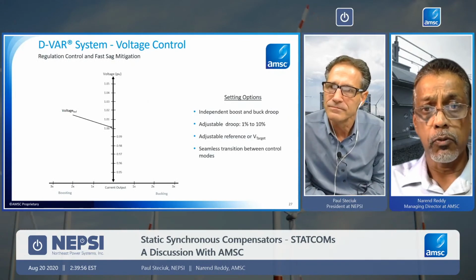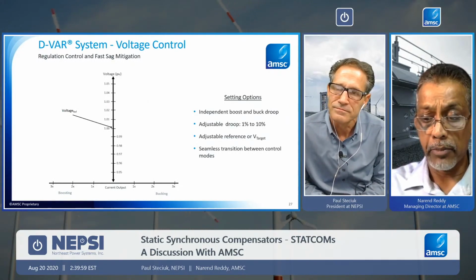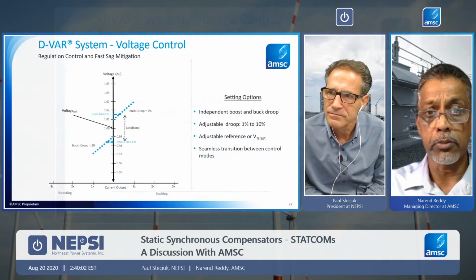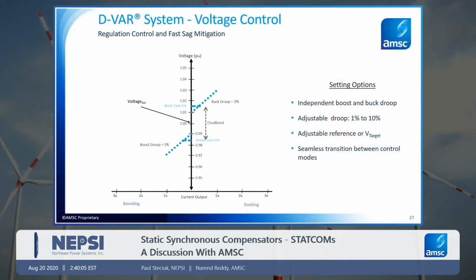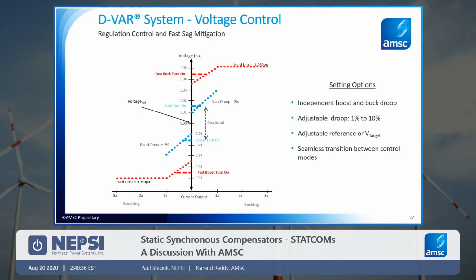Just to talk about voltage control basis, I'm sure you're familiar with this. This is really a drooped voltage control approach. There's a steady state control loop that's looking at, let's say, a medium voltage bus or a transmission bus, and it's looking for voltage changes over a longer period of time. It's managing this voltage on the capacitive and inductive side using some droop settings, depending on how aggressively you want to manage that voltage. This is operating on a longer term.